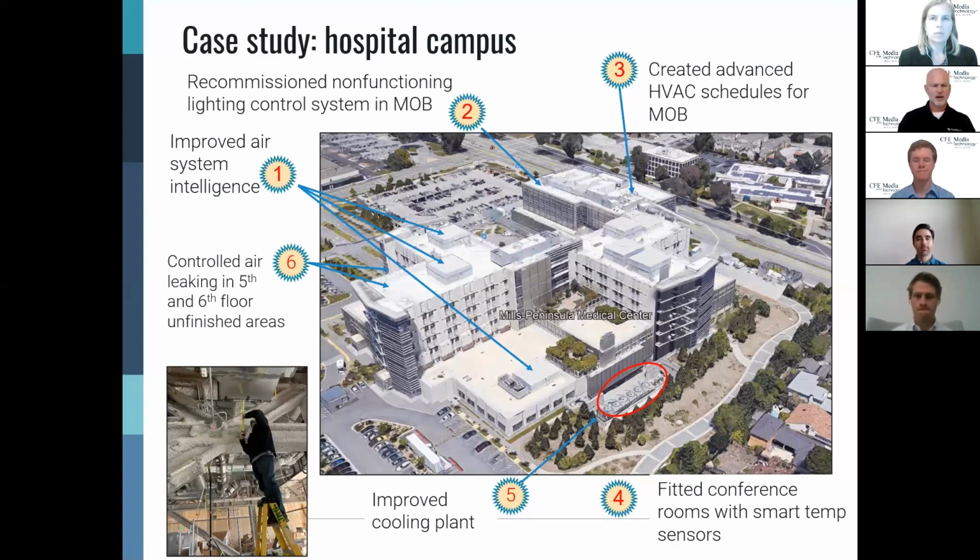So again, one of the biggest impacts that we made was really relooking at the controls in each room at a zone level and flowing that temperature and airflow data up to the air handlers and central systems, and then making smart decisions on it. So again, this idea of enforcing the vision, staying with the vision, revisiting the vision, and knowing when a smart building is trending off the track.